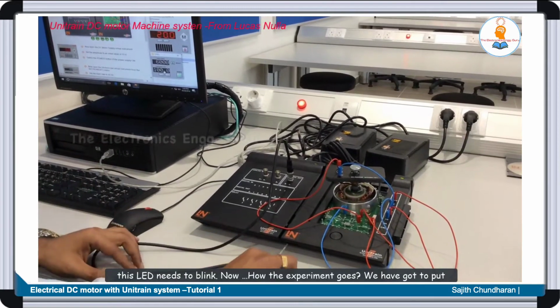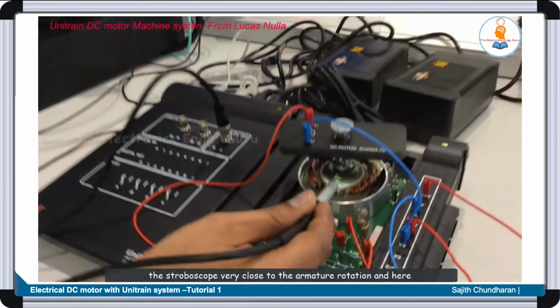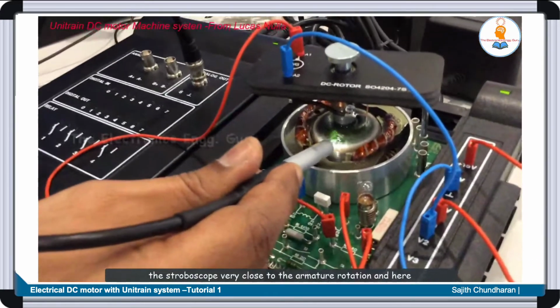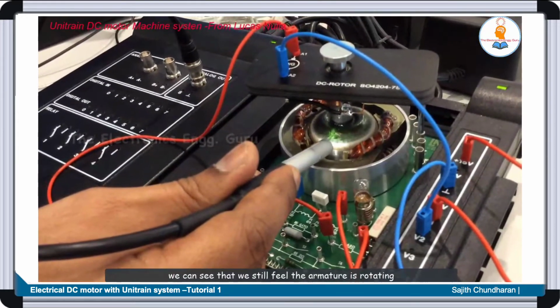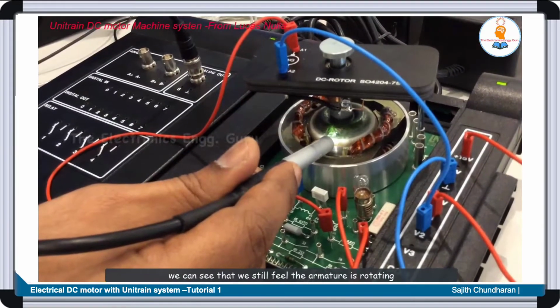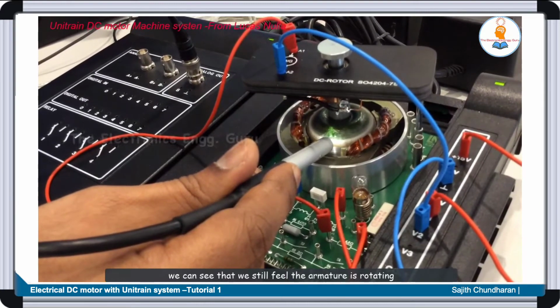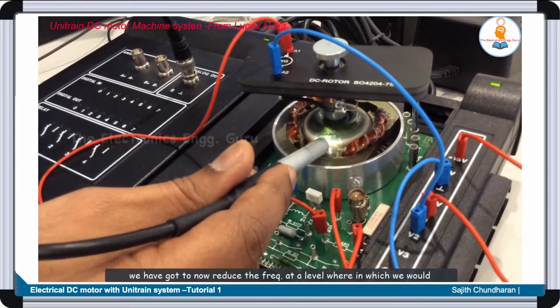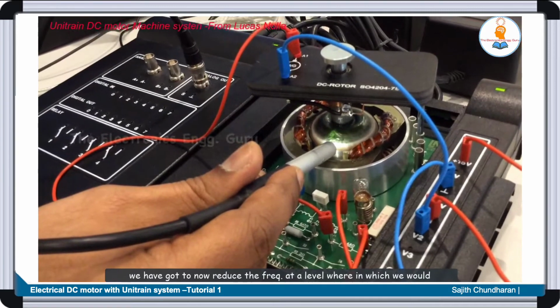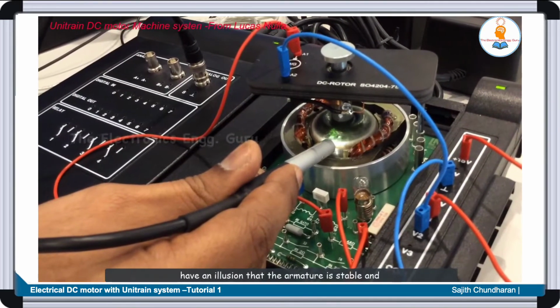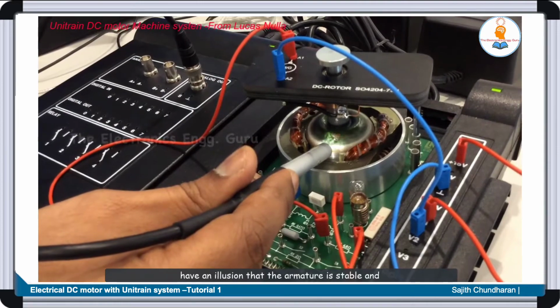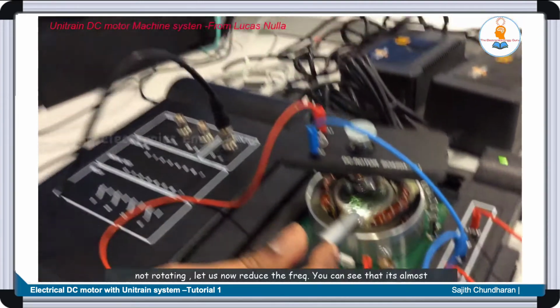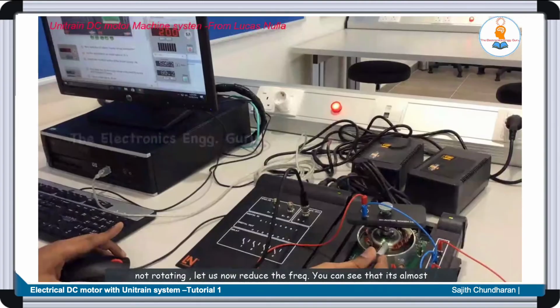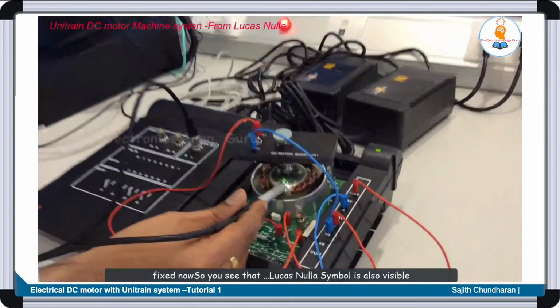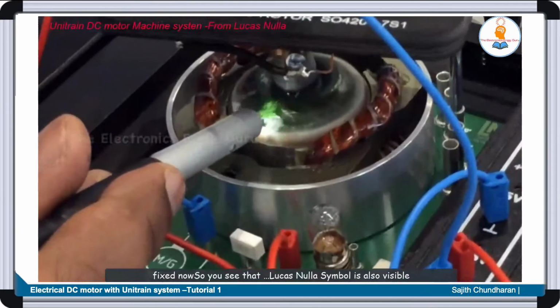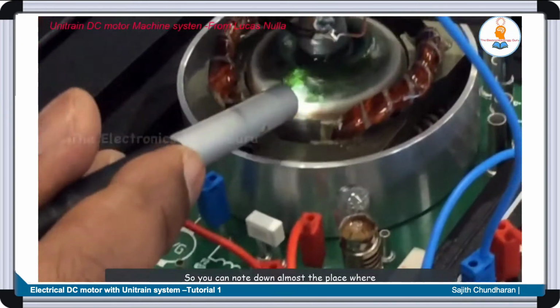Now, how the experiment goes? We have got to put the stroboscope very close to the armature rotation, and here you can see that we still feel the armature is rotating. We have got to now reduce the frequency at a level wherein we would have an illusion that the armature is stable and not rotating. Let us now reduce the frequency. You can see that it's almost fixed now. So you see that the Lucas Nülle symbol is also visible.